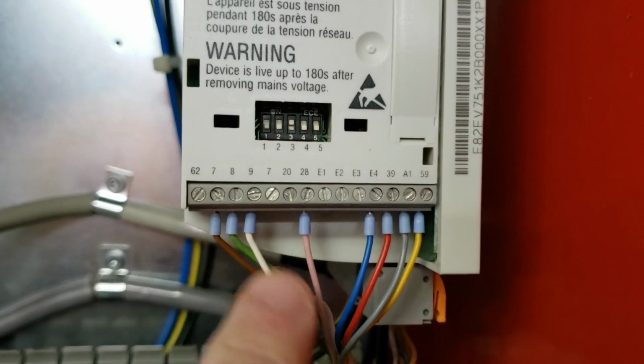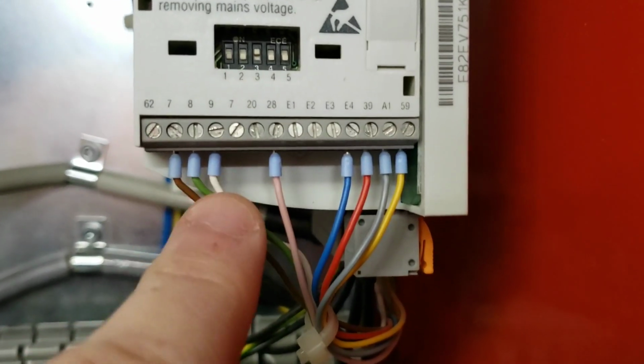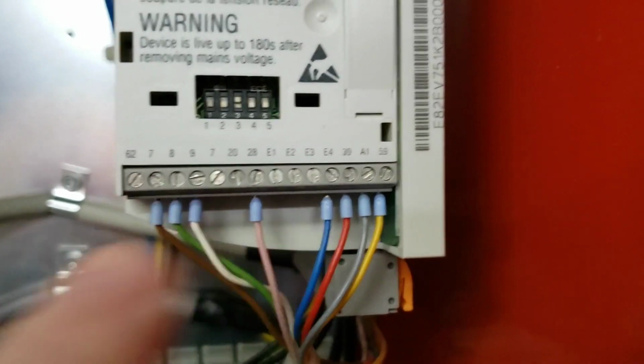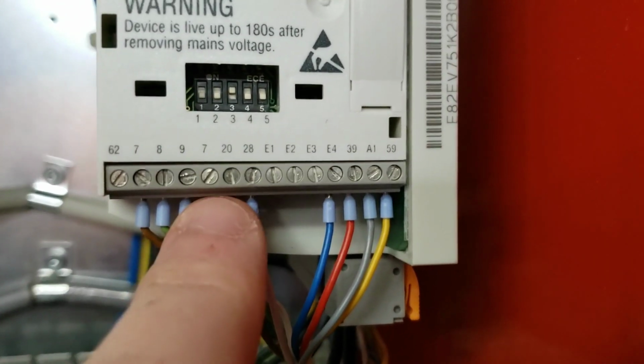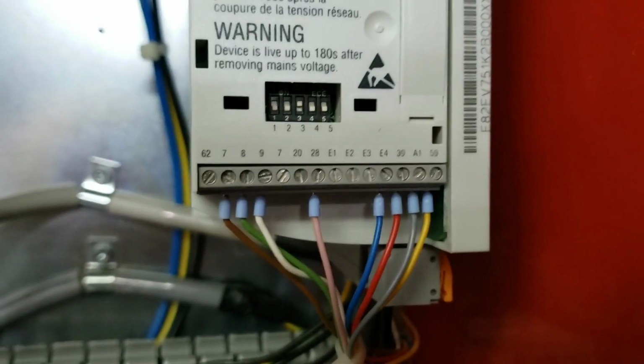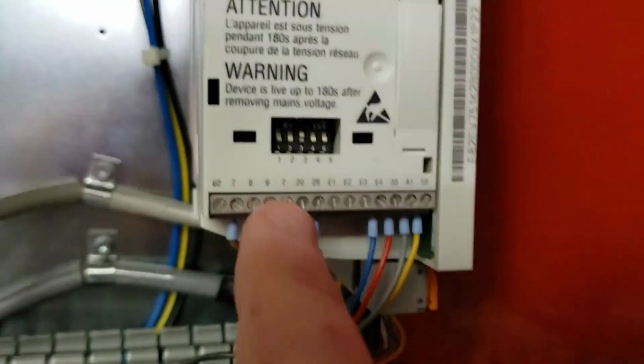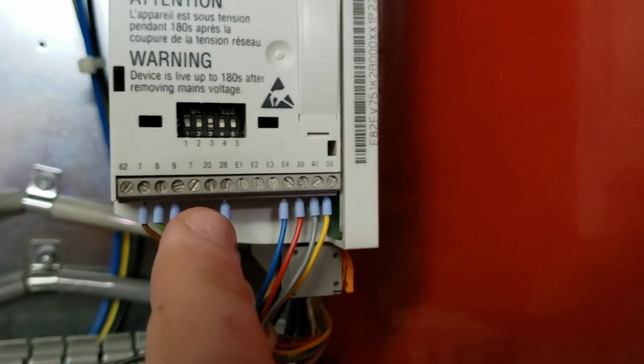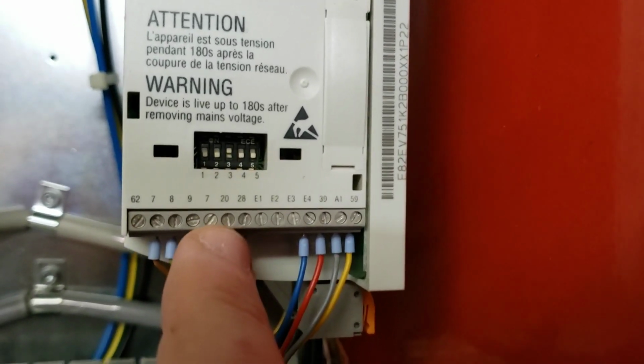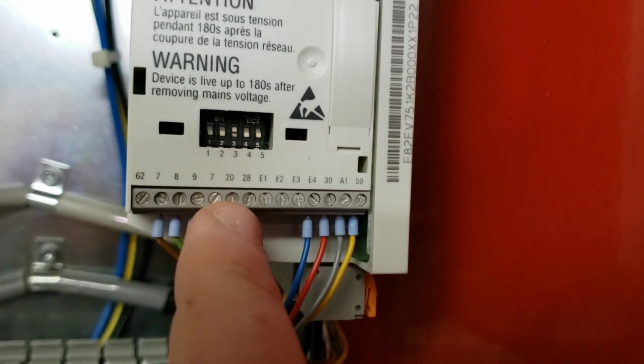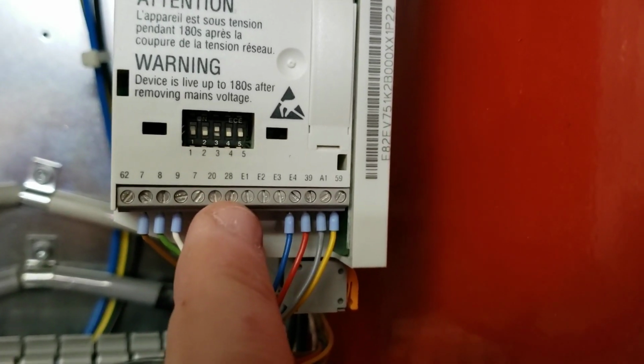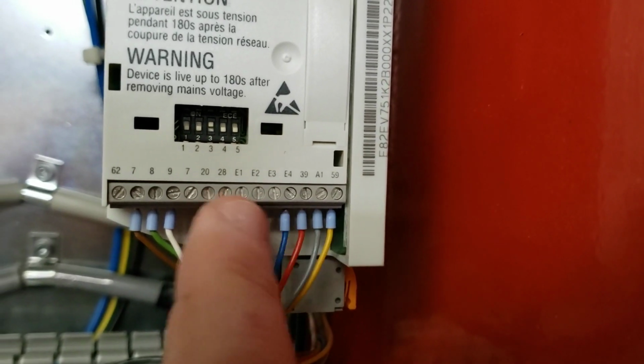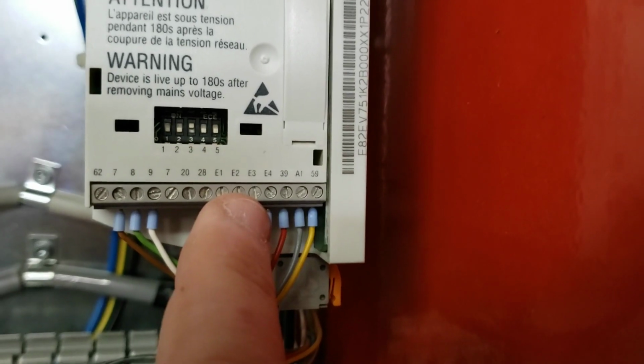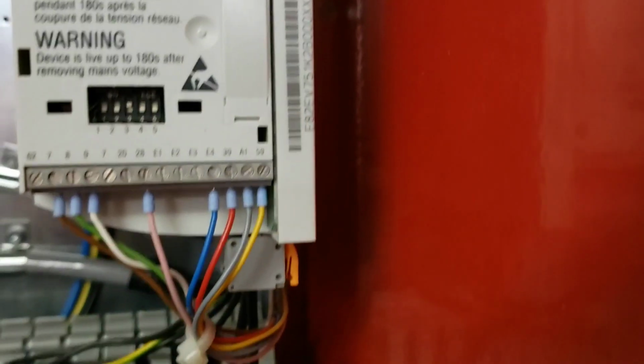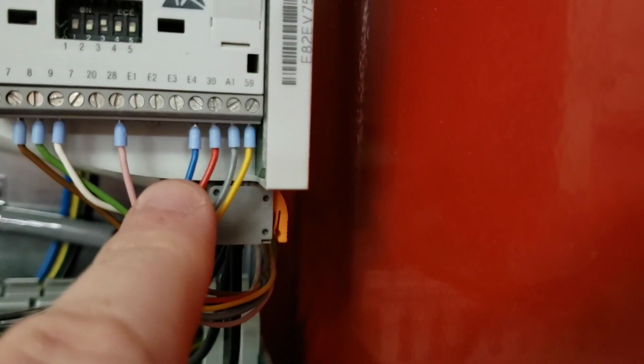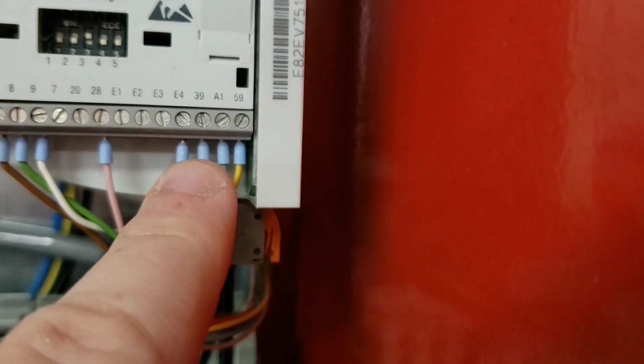Spot number 9 here is the analog potentiometer output. On a lot of other VFDs it's going to be 10 volt. This one outputs 5.2 regulated. And again, the 7 is ground. 20 is a voltage output for powering the I/O section. I'm kind of kneeling down, it's kind of tricky to hold myself up here. 20 is a set voltage output of 20 volts. 28 is the enable signal. E1, 2, 3, and 4 are basically miscellaneous accessories. Like there's a jog speed one you can set up, and in my case, E4 is the direction pin. 39 is the I/O common.